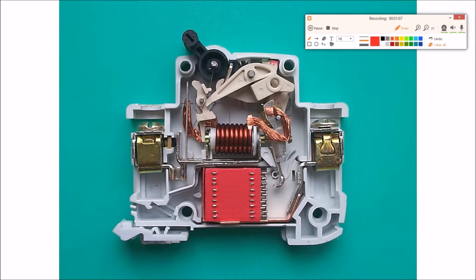The time delay fuse is replicated in the bimetal rod on the upper left of the circuit breaker. Because of the bimetal characteristic of this, when heated, it bends at two different rates on each side of the strip. Once the strip bends enough, it'll turn the switch off by pressing on here and breaking the switch here. There's one issue with breaking the circuit suddenly, and that's arcing of ionized air. The red box at the bottom alleviates this problem. It has a few metal plates that are insulated where any arcing can go to dissipate.